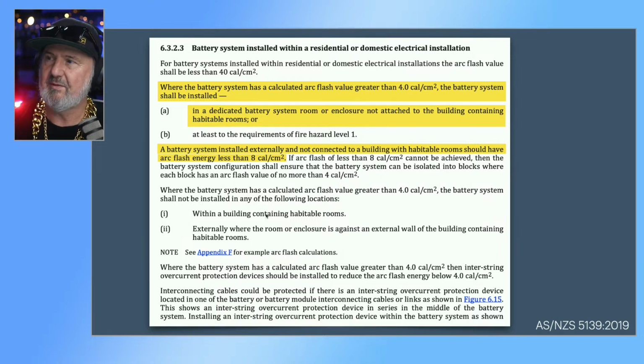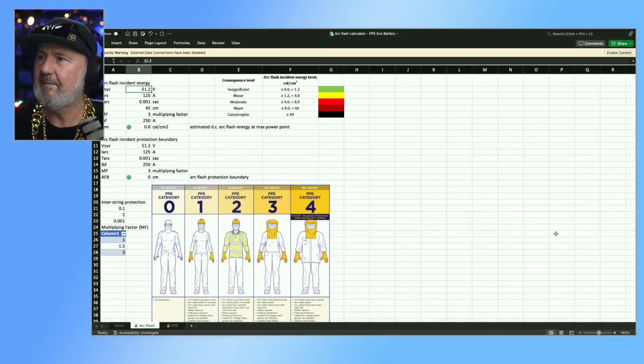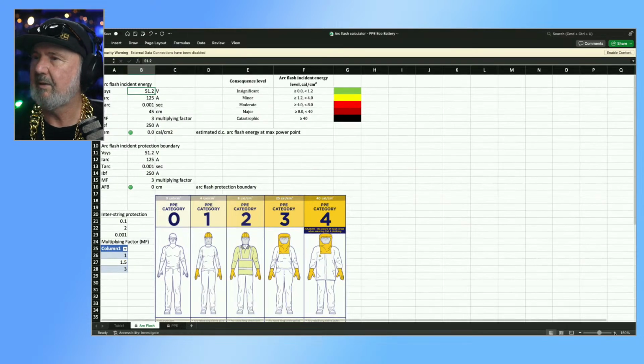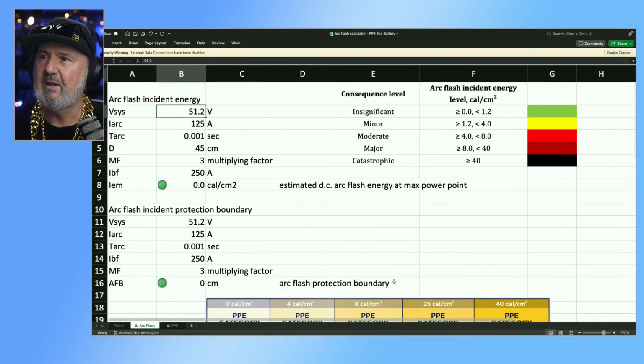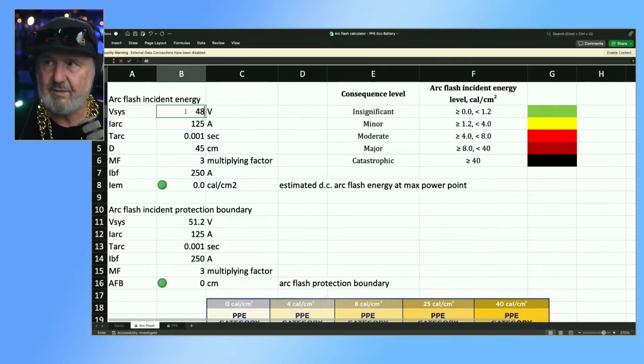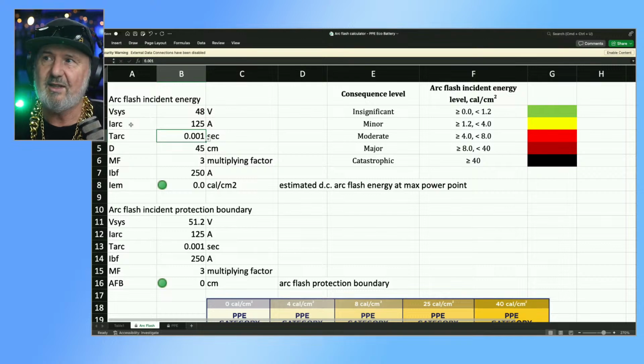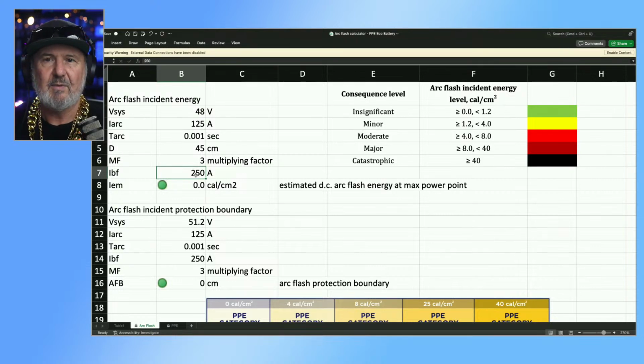But it's just a really simple spreadsheet with calculations. And if I bring it up here, here we go. It's probably a little bit small, but what you need to do is plug in some values. Now, let's take a lead acid battery system, just for contrast, because we're talking about lithium an awful lot. So I'm going to zoom in a little bit here. Okay, so we're going to do a lead acid battery system. Its nominal system voltage is 48 volts. You'll notice that the I arc, which is the arcing current, you can't click on it. We're going to skip over that, because what you put in is the bolted fault current, and that will calculate the I arc automatically. That's what the spreadsheet does for you. So the bolted fault current is the peak current when no overcurrent protection is in place, you're circumventing any overcurrent protection on the output of the battery system.